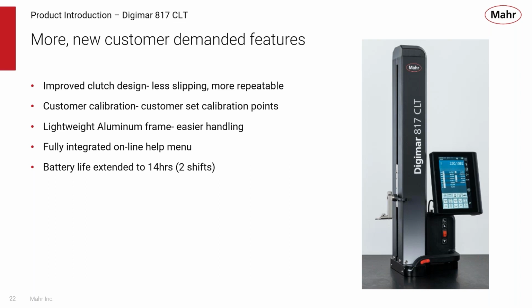One of the great things about the new 817 CLT is that it can be calibrated and adjusted by the customer, so you no longer need software, a computer, or a specific measuring artifact to calibrate it. The customer can set their own calibration points and very easily and cheaply calibrate the 817 CLT in-house, without purchasing additional accessories or sending the gauge out for calibration. It also has a fully integrated online help menu.